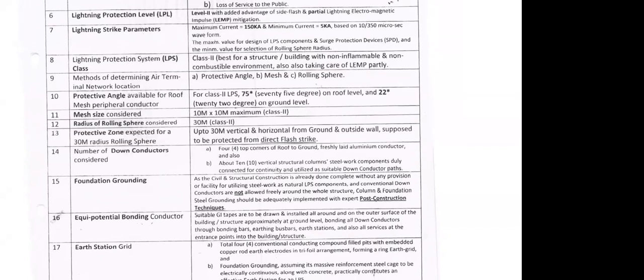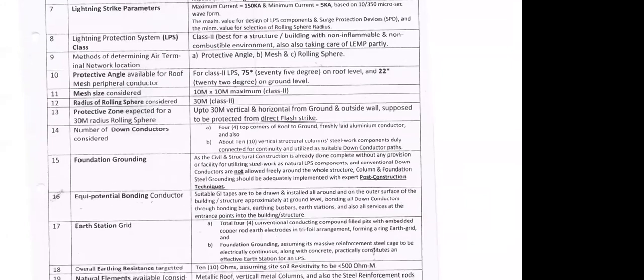Now, again, it is important that foundation grounding becomes very important, that whether the particular building can allow this lightning protection to be terminated in the building itself. That is also possible. If the reinforcement of the building is too high, then we can use the reinforcement rods of the building, but it is not a good technique and it is better to avoid. Equipotential bonding conductor.